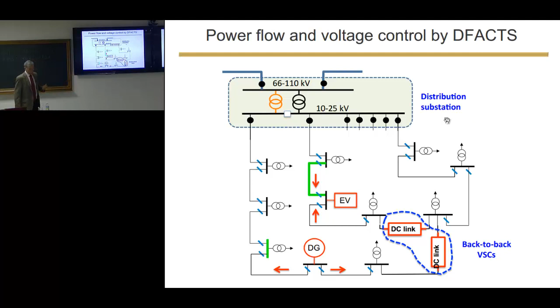Another idea that we have also been developing, and we are now almost at the industrial production level, is changing the mechanical taps of the secondary substation, the secondary transformer. They have mechanical taps. They can change mechanically plus minus 5% of the voltage level on the medium voltage side. This is a dry transformer. You can see here the triangle, the delta connection. Replace the mechanical switches by thyristors, okay? This would give you flexibility to change the taps, which are fixed. You can see the mechanical bridge. This mechanical bridge is fixed.